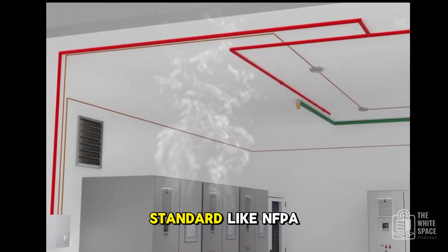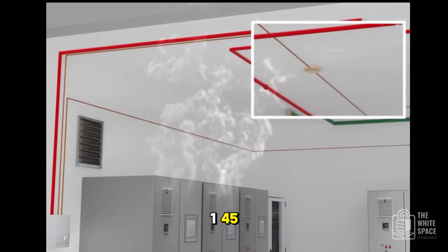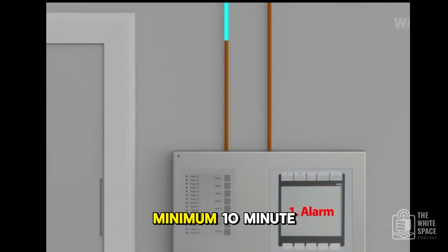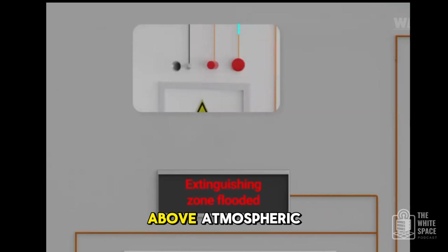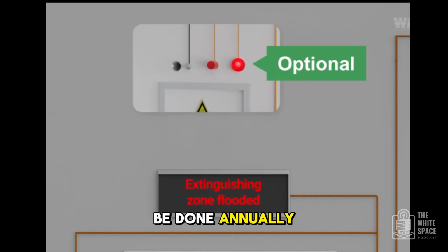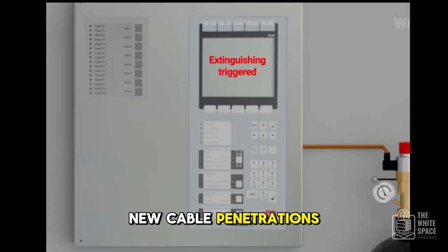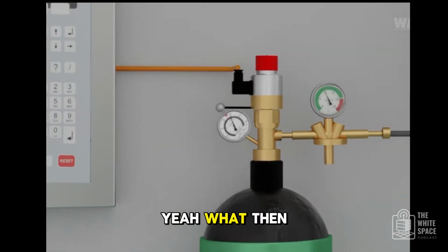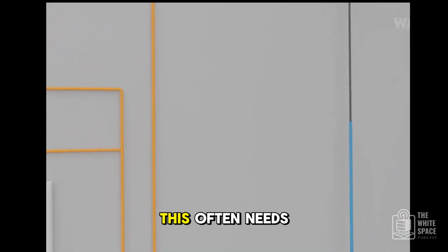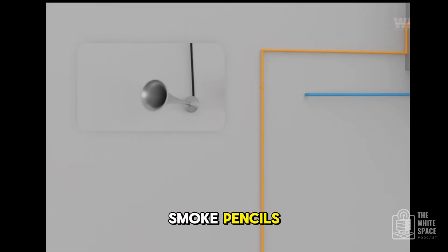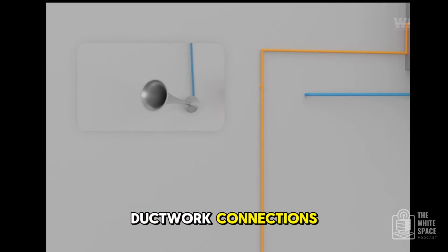Generally, yes. Standards like NFPA 2001 or ISO 14520 require that minimum 10-minute hold time, maintaining a pressure equivalent often cited as 25 pascals above atmospheric. This test must be done annually. Annually, or anytime significant changes are made to the room: new cable penetrations, modifications to walls, doors, windows. If the room fails the test, what then? You have to find and seal the leaks. This often needs a specialist. They might use smoke pencils or other methods to pinpoint where air is escaping around door frames, cable holes, ductwork connections, and then seal them properly with fire-rated materials.